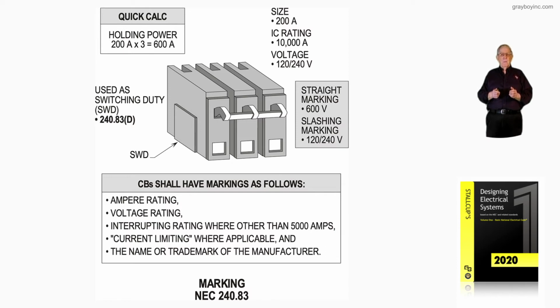being replaced. And the grounding part of the system is very important, as 15.9.9 of 70B states. And then when we review chapter 14 of 70B, we're actually referred to 240.83 to replace breakers so that we don't make a mistake and put a slash mark breaker on a system that it's not supposed to be put on, because it's only approved for solidly connected grounded systems.